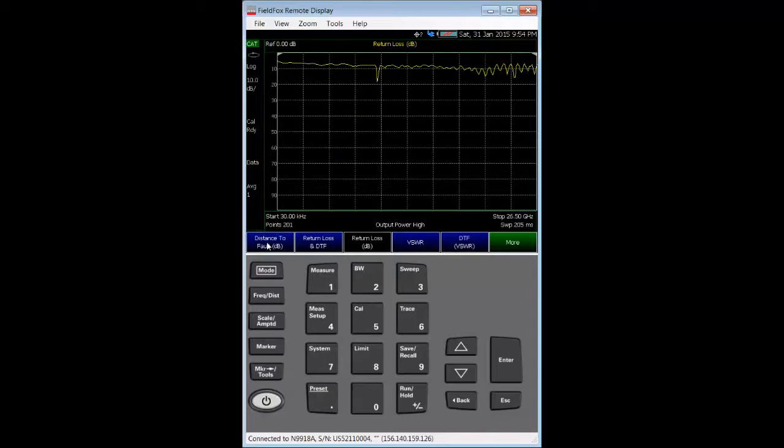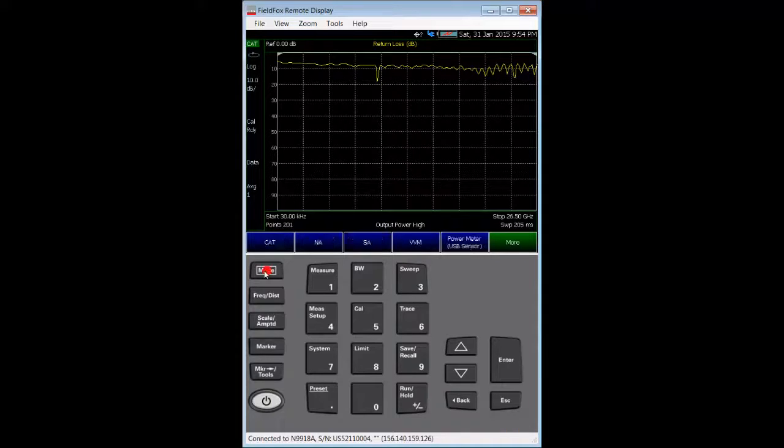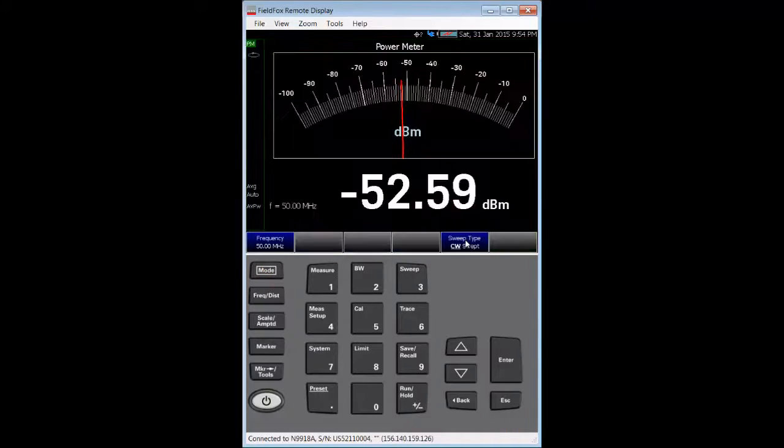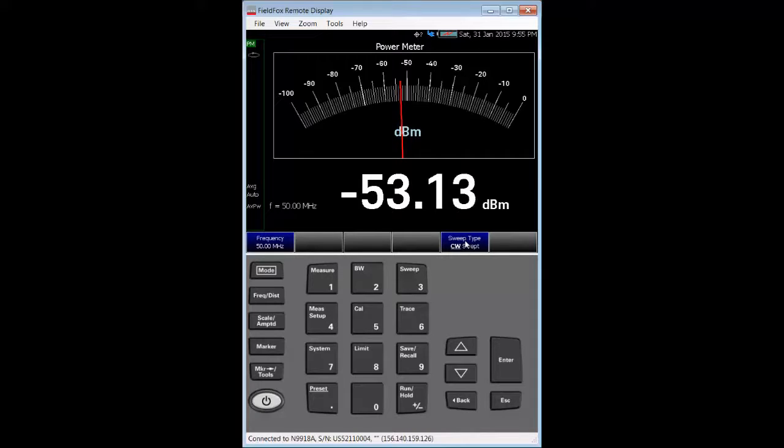Next, we press the mode hard key, followed by pressing the power meter USB sensor soft key. A U2002A USB power sensor is connected between FieldFox's USB port and the IF signal output port of my frequency converter.